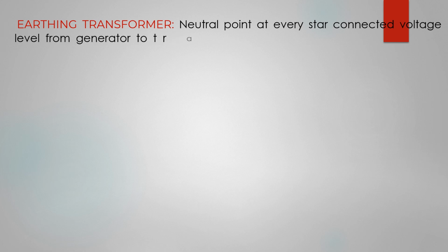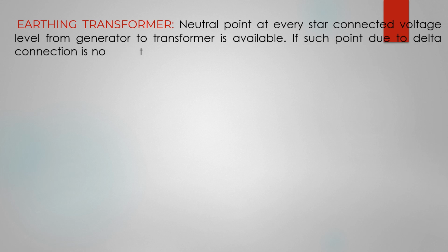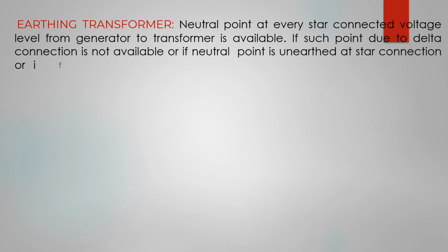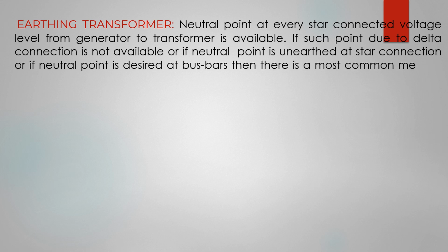A neutral point is available at every star connected voltage level from generator to transformer. If such a point is not available due to delta connection, or if the neutral point is unearthed at a star connection, or if a neutral point is desired at the bus bar, then the most common method is employing an earthing transformer, that is, a zigzag transformer.